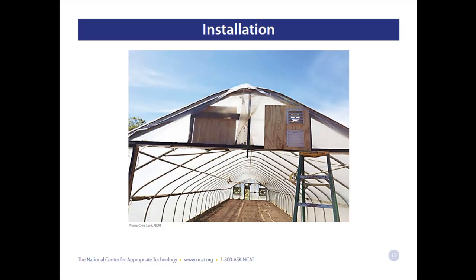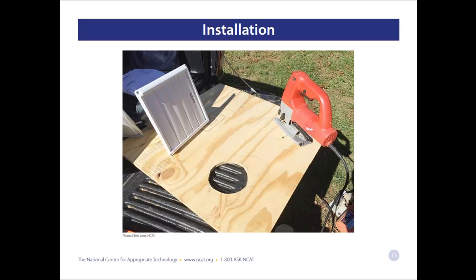The plywood that's placed on the inside of the high tunnel is for the heat recovery ventilator to hang on. And this plywood that's placed facing the camera on the outside of the tunnel here in this slide is for the vent hoods themselves. The vent hoods are placed by cutting these circles into the plywood and then attaching the vent hoods to the plywood. There's a small metal ductwork behind each vent hood that slides through these holes, and then they get screwed to the plywood. And then the plywood, like you saw in the previous slide, gets attached to the greenhouse.